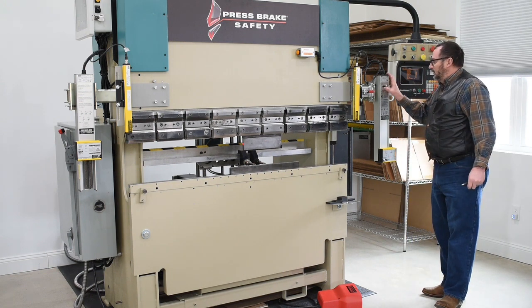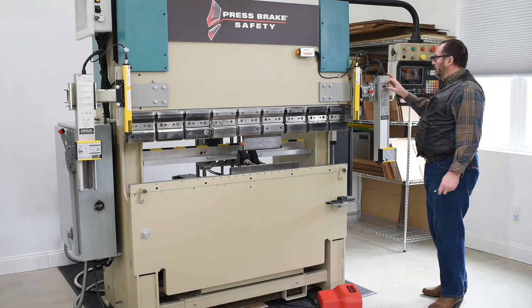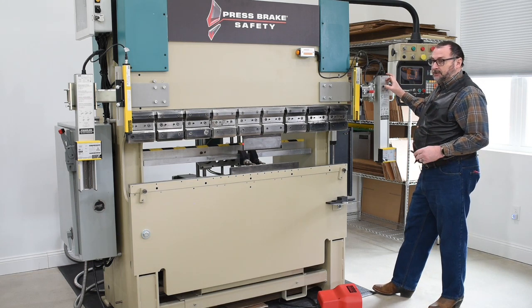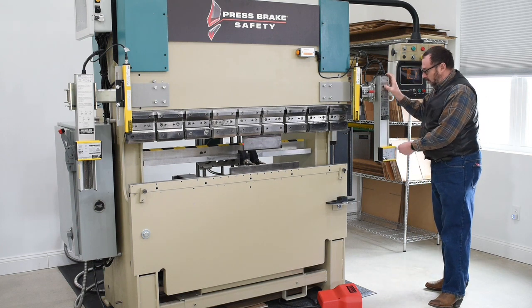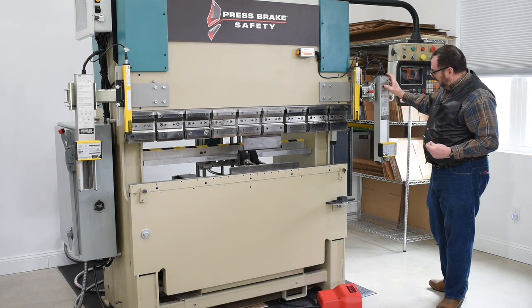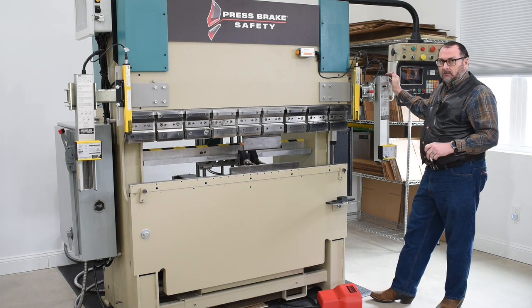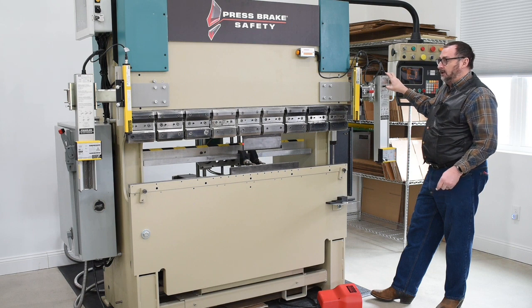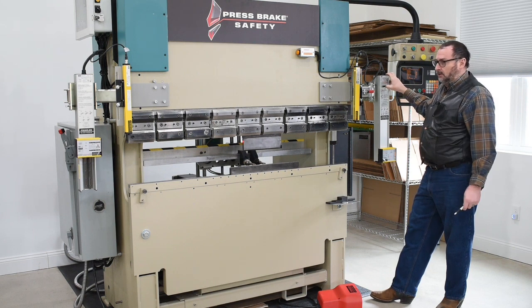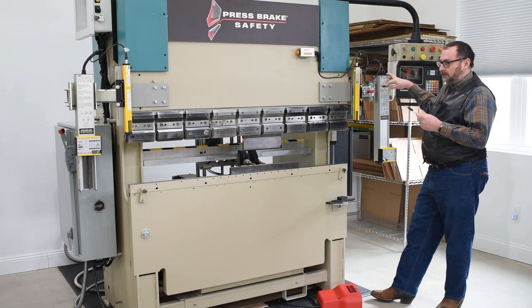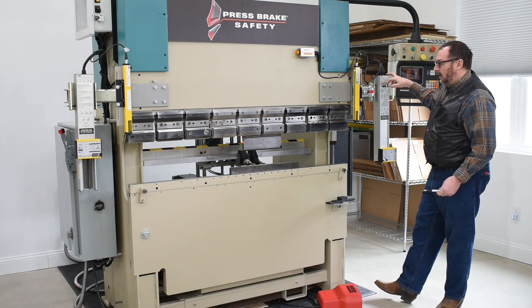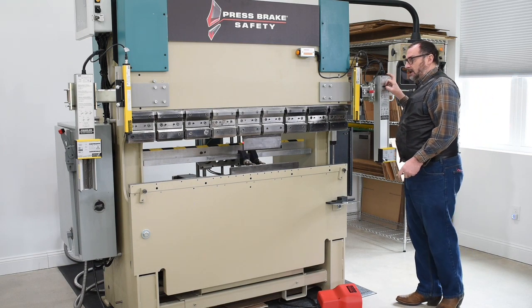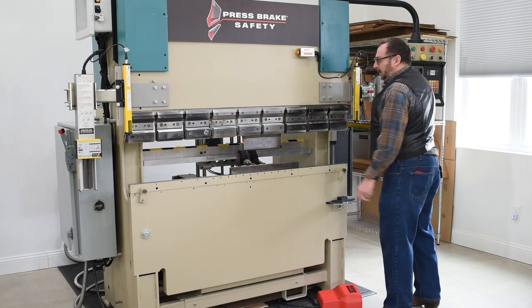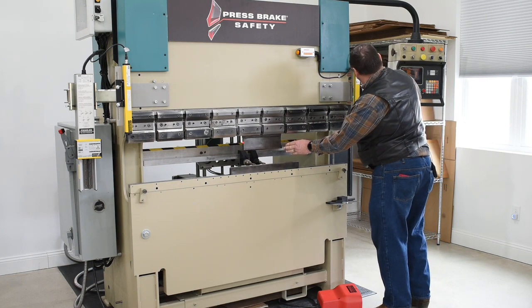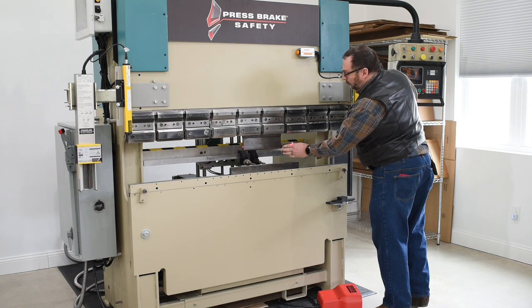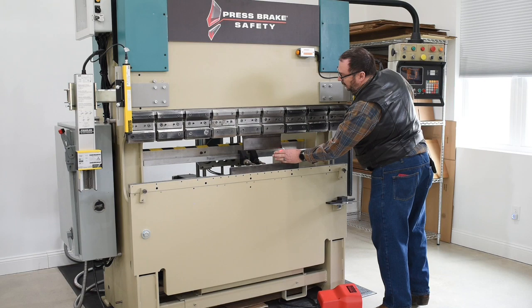Now, as I said before, if we turn the key switch on and we push the push button and hold it, the receiver will climb. If we push and release the black button, the receiver automatically goes downward. If we push the toggle switch upward, the transmitter will go up. Toggle switch down, the transmitter will go down. So with this knowledge in mind, we'll use the toggle switch, and we want to make sure our magnet's in place, and we want to position the transmitter using the toggle switch to where it's just below the tip of the upper tooling.